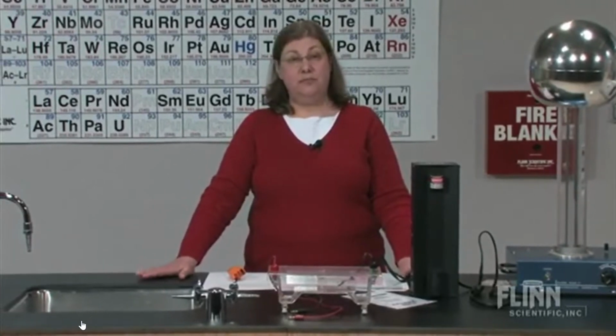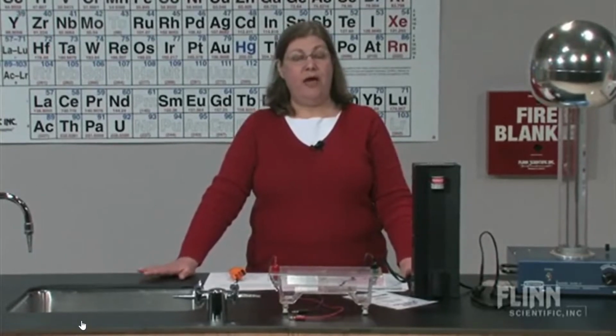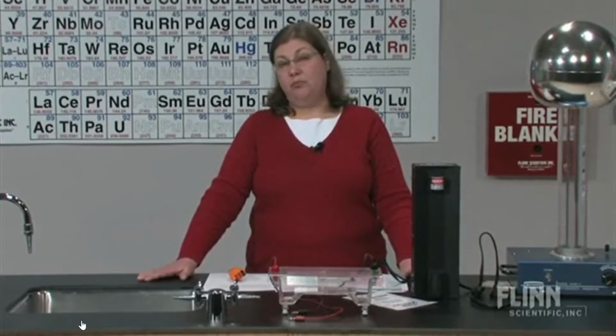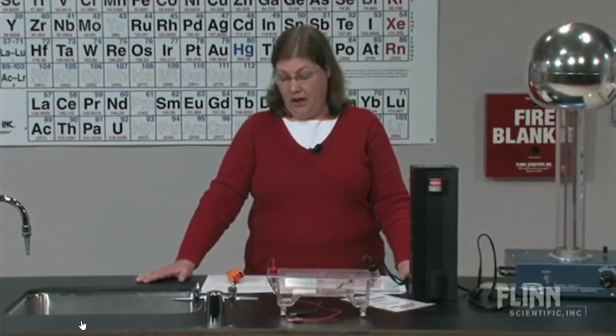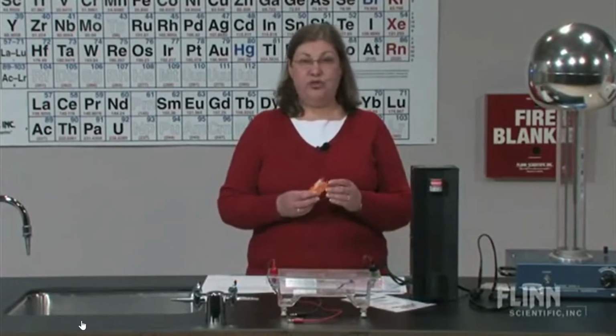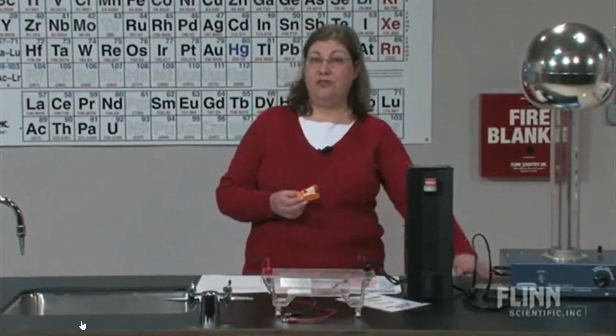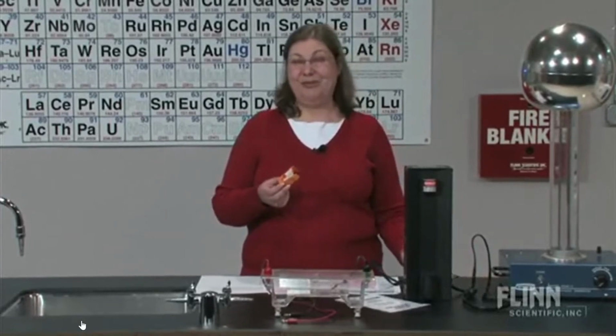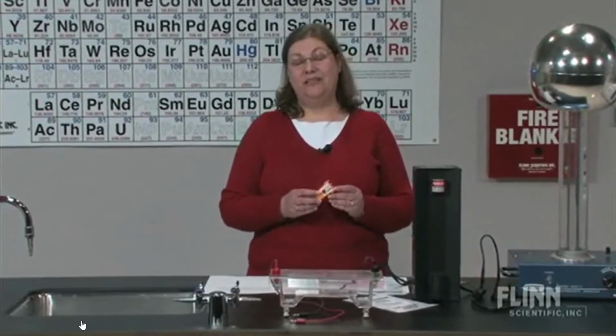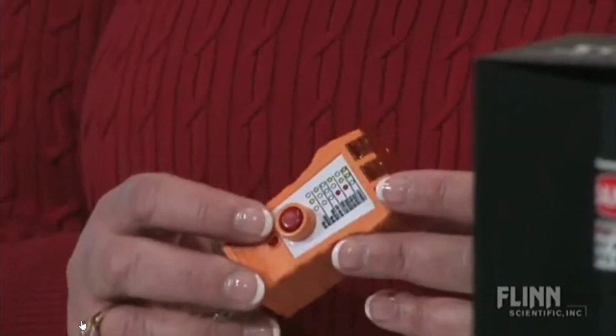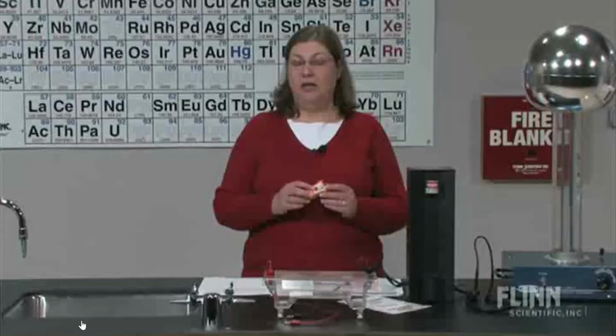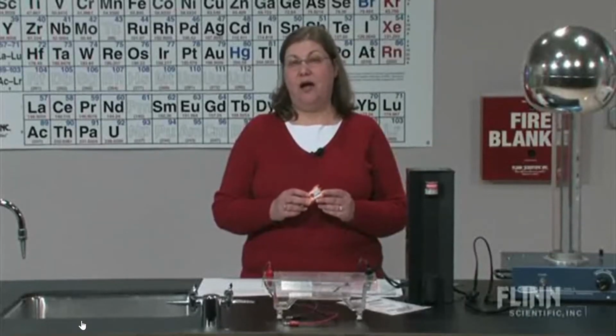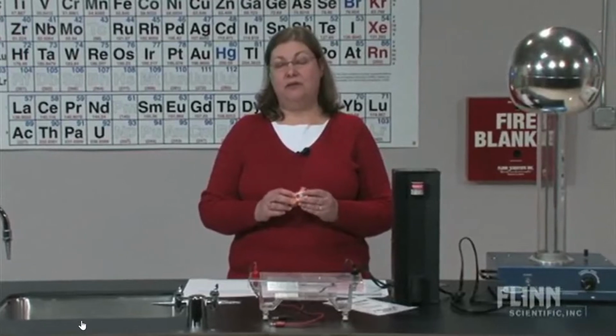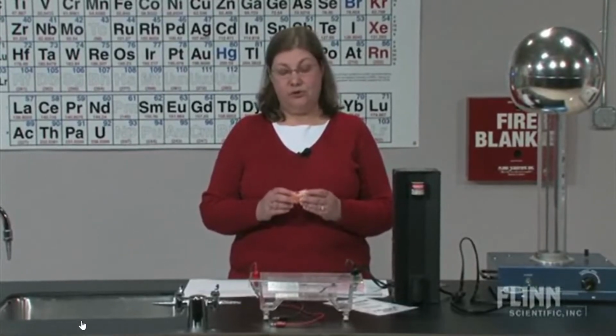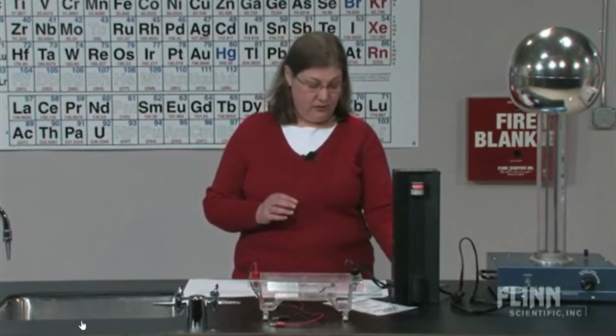Second, you need to inspect your circuits at least yearly. In a recent inspection at a local high school, they found that 30% of the circuits were wired improperly. There's a small device called a ground fault circuit interrupter tester, or receptacle tester, that can detect up to 6 different possible wiring errors. This is a very common problem found in laboratories across the country, so we urge you to check your circuits at least yearly to make sure they're wired properly.